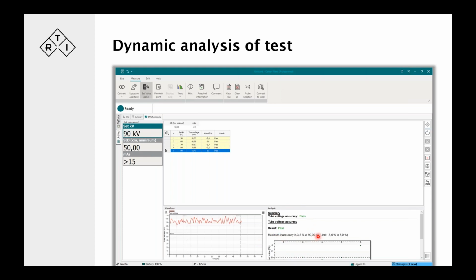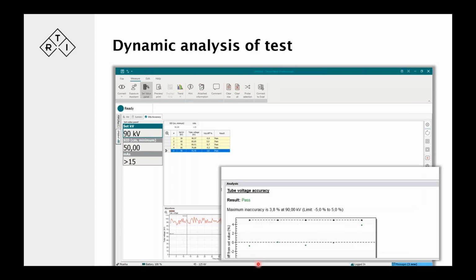And to your lower left or lower right, we see that we have a result pass and some more information about what's going on. The maximum inaccuracy is 3.8% at 90 kV, which is this point right here. And the other, see these green dots, is a graphic plot of the deviation from 0% of the measurement.